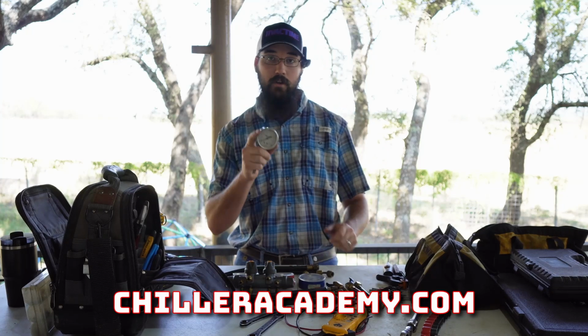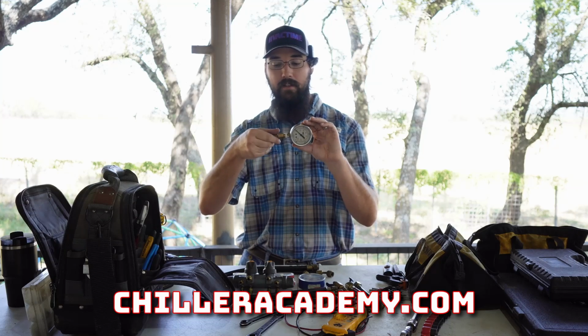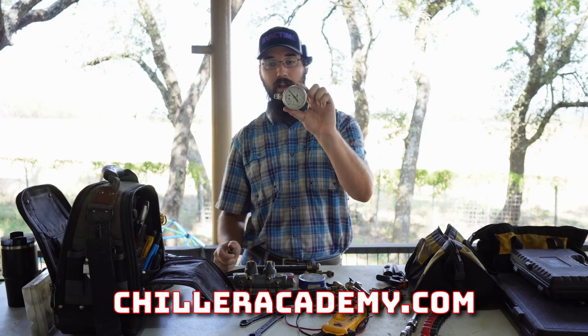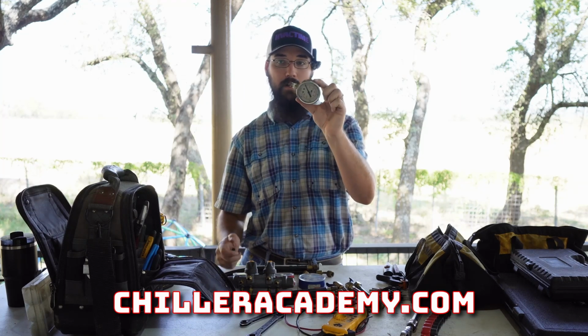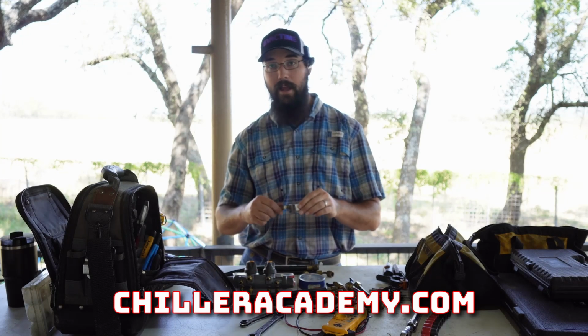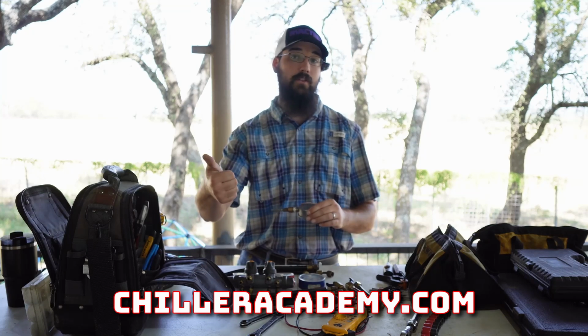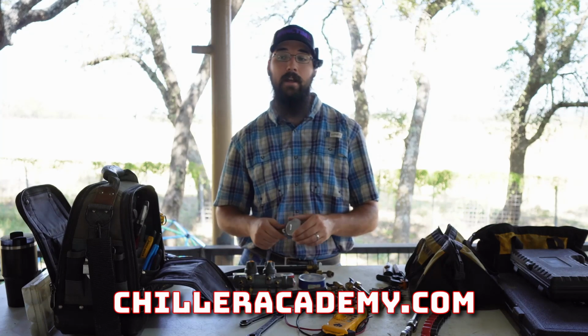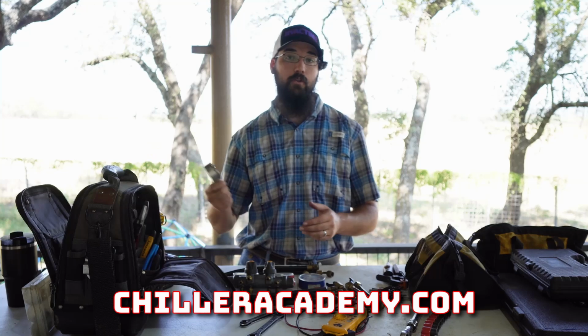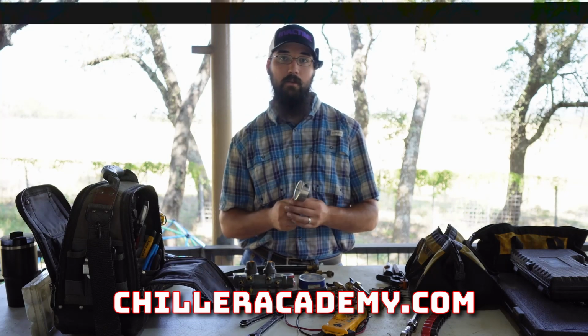But having a set of water gauges is critical. If I have a system that does not have PTs, then I just thread the fitting off and thread it into a pressure tap somewhere. Lots of times they may already have a pressure gauge sitting in there, but that gauge, either you can't trust it, you don't know if it's calibrated or not, or it's just obviously busted. You can take one that is calibrated and use it in there.